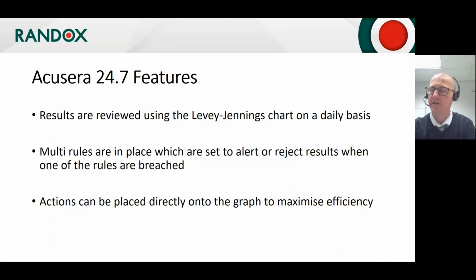They also have a selection of multi-rules that are from Westgard. These are actions using a toggle button, and essentially they allow you to set your rules for your laboratory however you want it. We usually set them to alert or reject. It's nicely color coordinated, so anything that would come up as an alert would be yellow. Anything that comes up as reject would be red. Obviously, if it's a reject rule, you shouldn't be processing samples, so you'd stop and troubleshoot. These actions again can be placed directly onto the data point on the graph to maximize efficiency, and also again help with your tracking and trending, and help with any investigations into troubleshooting failed QCs.